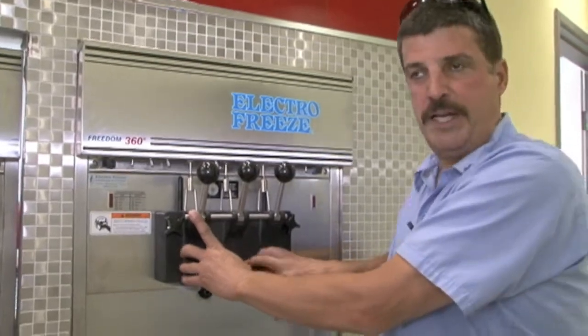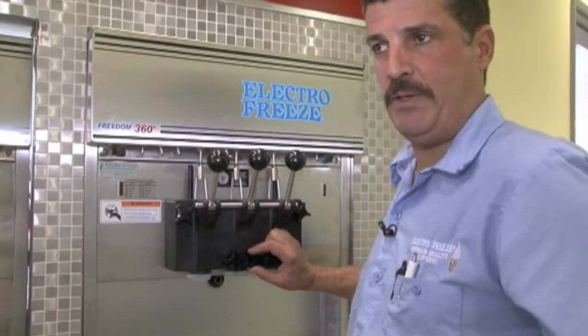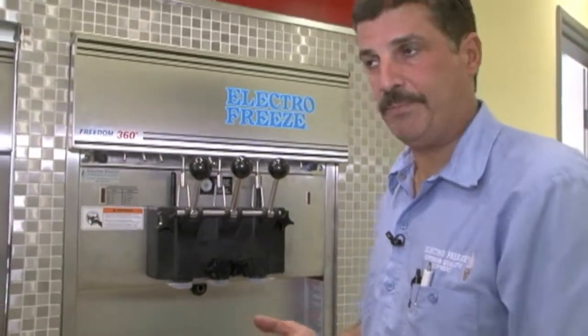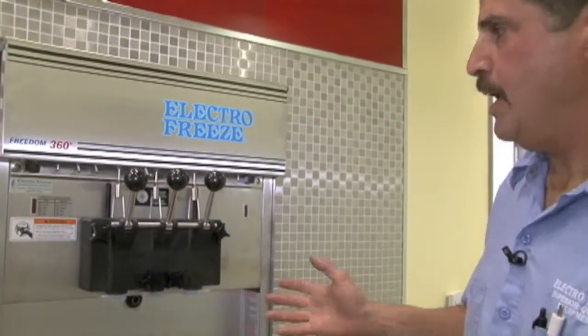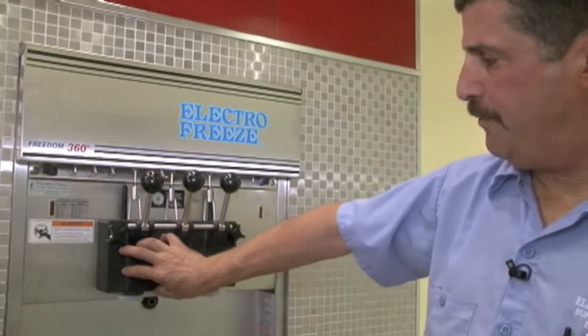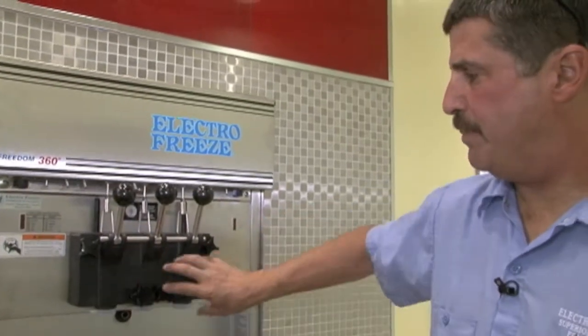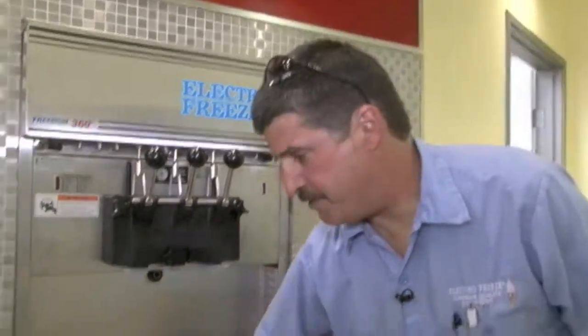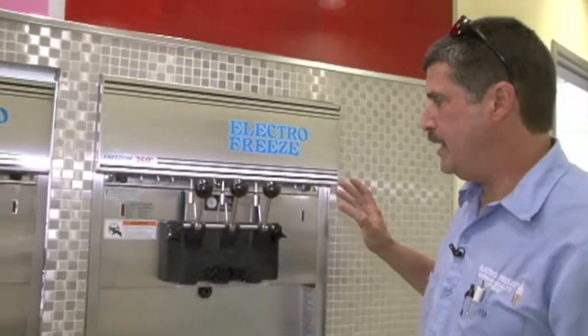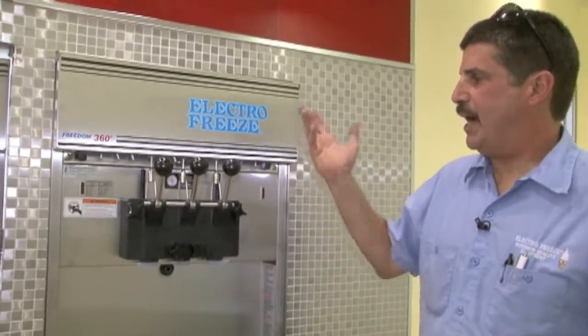So the machine doesn't have to work all night. It's not going to beat up your product all night because no one's pulling any product out. You don't have product breakdown. Keeps it below 41. It's set at 38 degrees in the barrels. And of course your refrigerator will be on all the time, and that's your night operation.